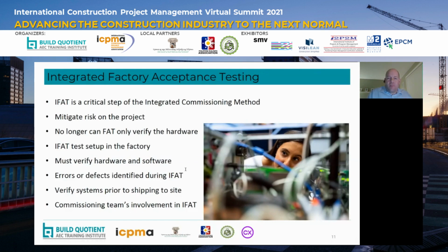If instead someone decides that it's not effective to send an operator to the factory to witness this, then the operators are only seeing the screens for the first time as equipment arrives at site. And at that point in the project it is way too late to be making any changes to the HMI screens or function of the system. Essentially, those issues have to be deferred until a later point in time, meaning that the operators aren't necessarily pleased with how the HMI screens are laid out. And that's never a good situation to be in. We want to get that input much earlier in the sequence.